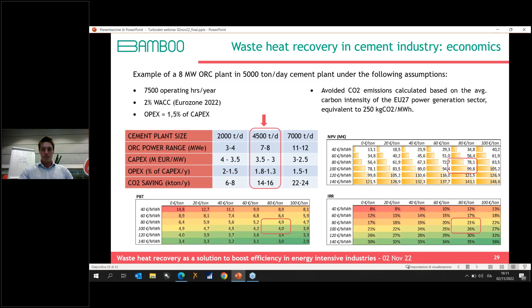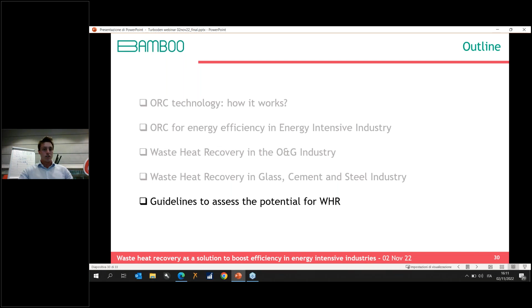So to sum up, let's see some guidelines to assess the potential for waste heat recovery, in order to understand which are the main parameters to look at when you want to discuss the installation of such a plant in your system. So the good feasibility, typically, is if you have a high efficiency of the thermodynamic cycle, which means that you have a high temperature of the waste heat sources, or low temperature of the cooling sources. With high temperature, we typically mean at least 300 degrees C and at least 3 megawatt thermal available from your heat sources. And with low temperature, you are typically considering an average ambient temperature for European countries, which is around 20-25 degrees C.